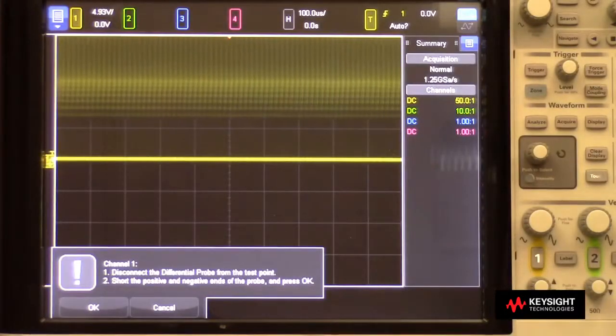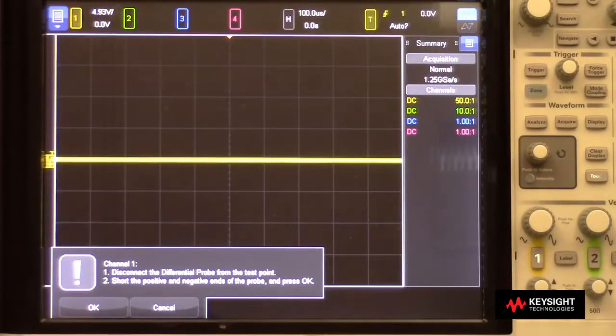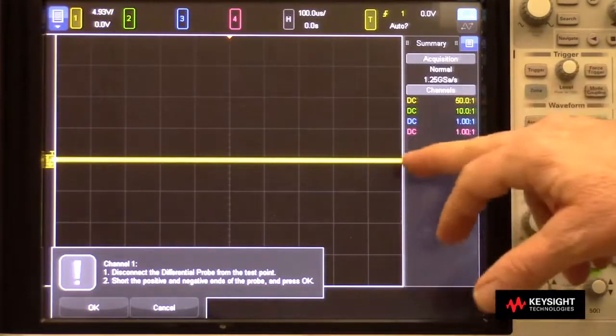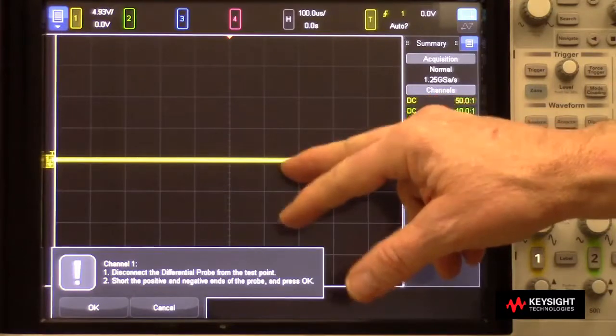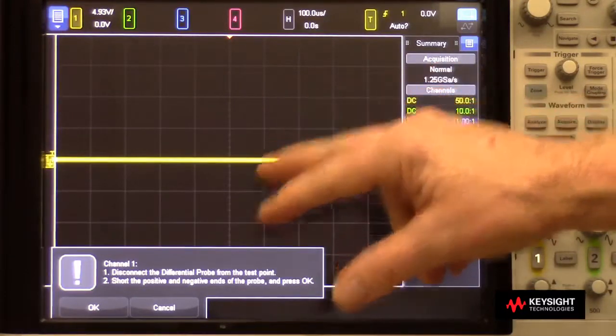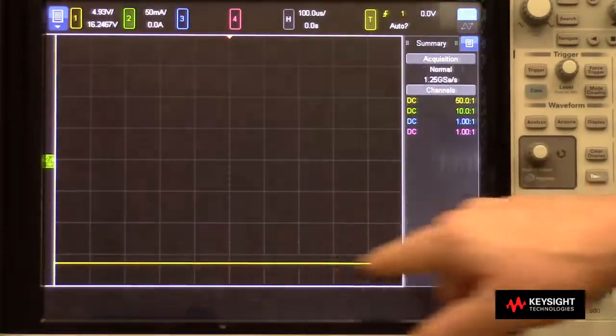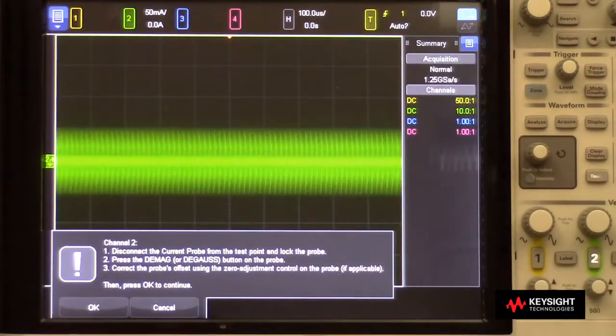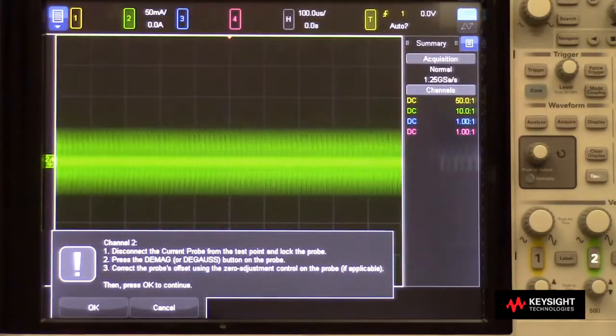Next, it instructs me to disconnect my voltage probe from my device under test, short the tips together, and here's zero volts or what should be zero volts. It's going to measure what it is and then compensate for it. So we'll press OK. It turns on averaging, makes a very accurate measurement of the average voltage here in that time window. I'll connect my voltage probe back up.